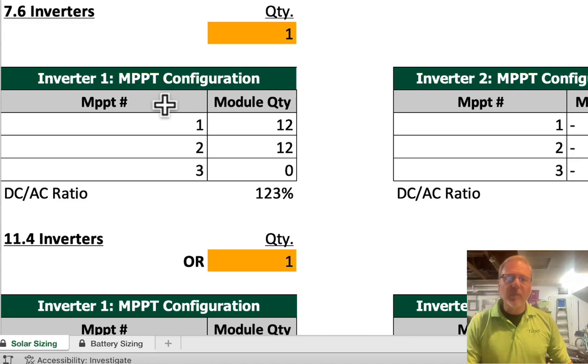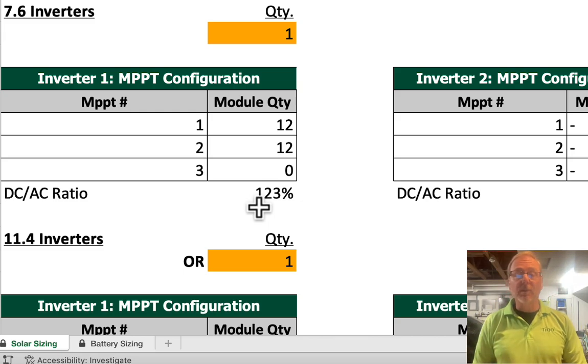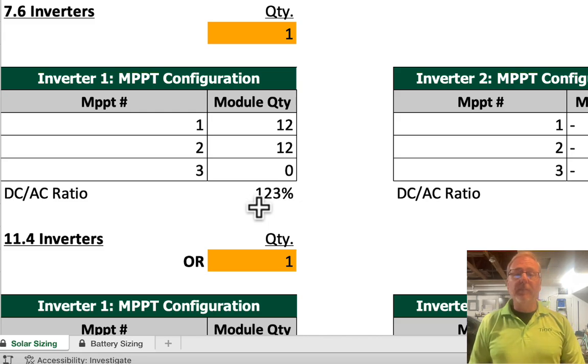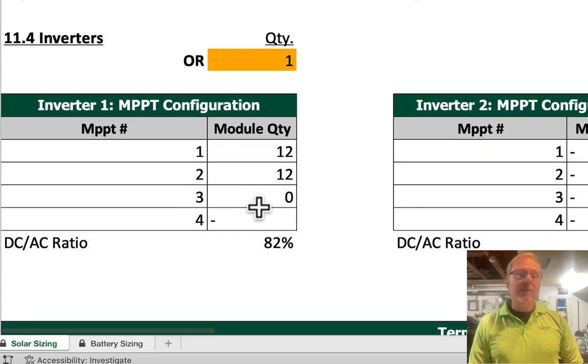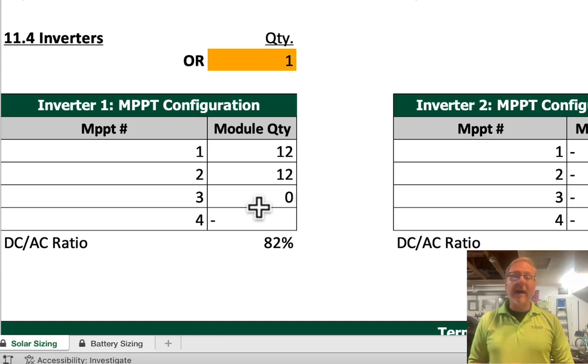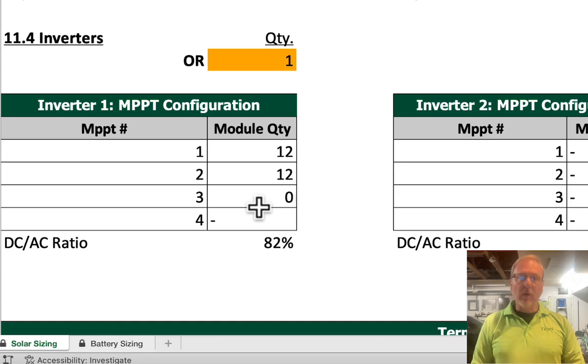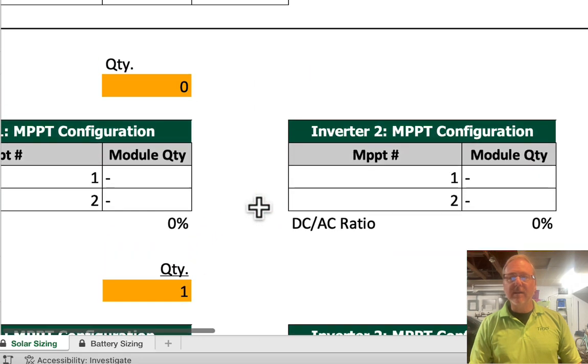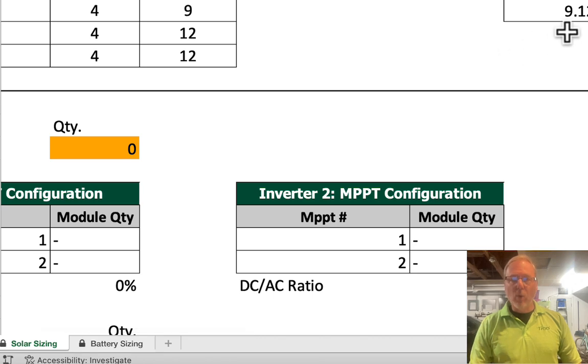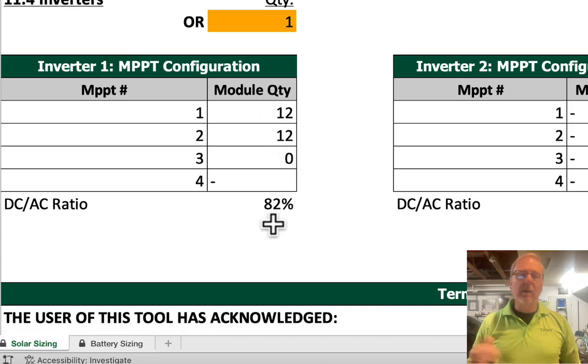If we look at the 7.6 kilowatt inverter, it says you have 24 modules — we're going to do two strings of 12, and you are at a 1.23 DC to AC ratio. That was a pretty common setup for a 1.2 ratio. If we go down to the 11.4, you can do that as well — two strings of 12, but you're at a 0.8 to 1. That means the array is undersized relative to the inverter nameplate value. The array size was 9.12 kilowatts, which is way less than 11.4.